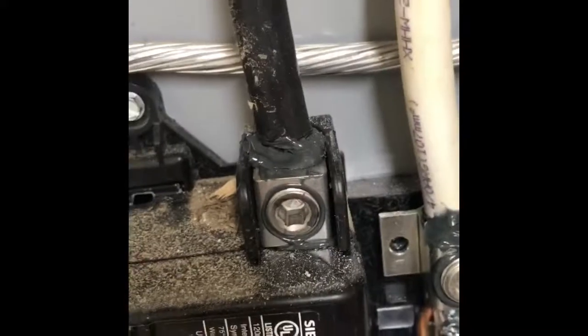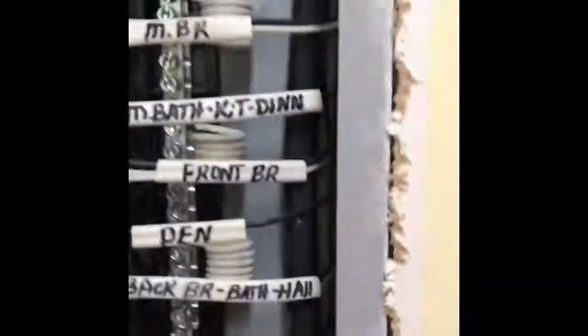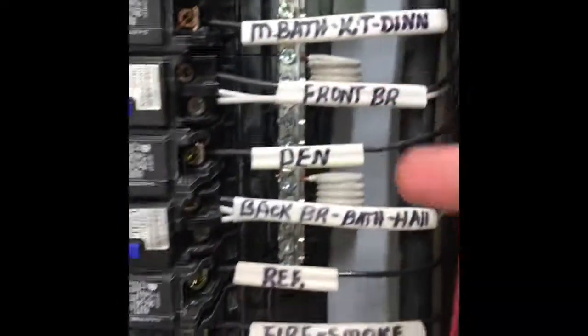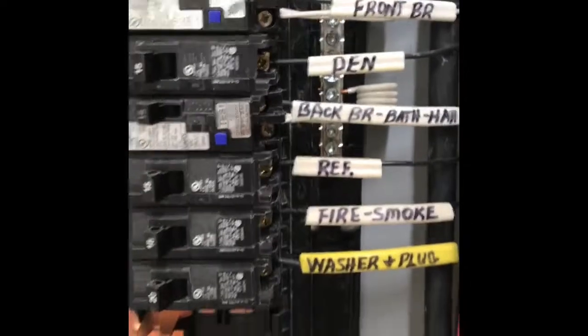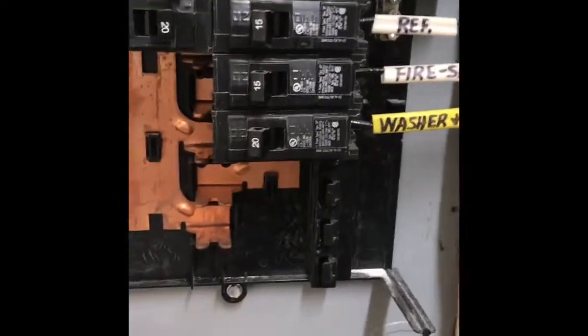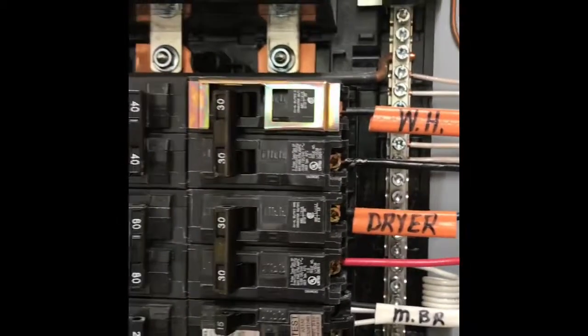There's anti-oxidant, anti-corrosive paste they added. The panel's free of debris. The proper AFCIs are going to be on the bedrooms, which is still only the requirement in Tennessee. I know some states require a lot more than just the bedrooms. The water heater has a lockout, just in case you want to lock the water heater out, like if you're going to turn the power off or the water off to the house, you want your hot water heater off. But this panel is something, honestly, home inspectors don't see much.